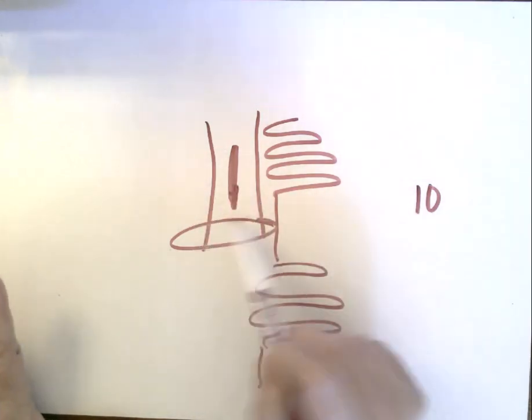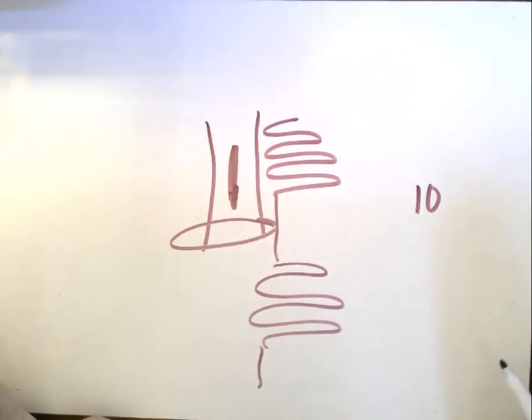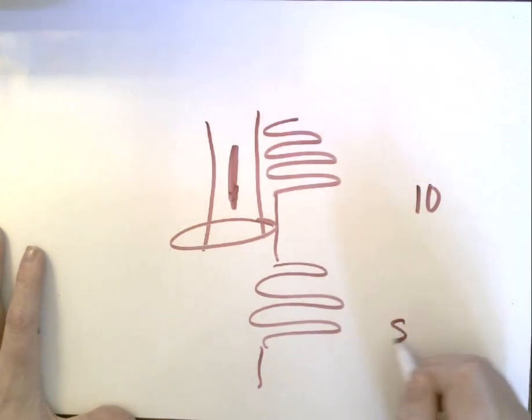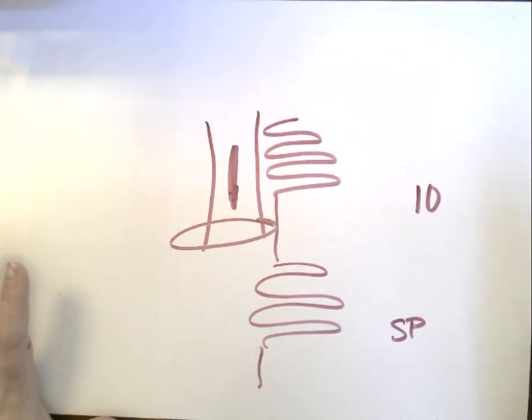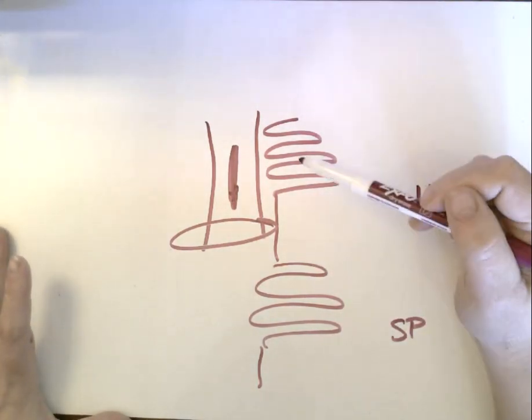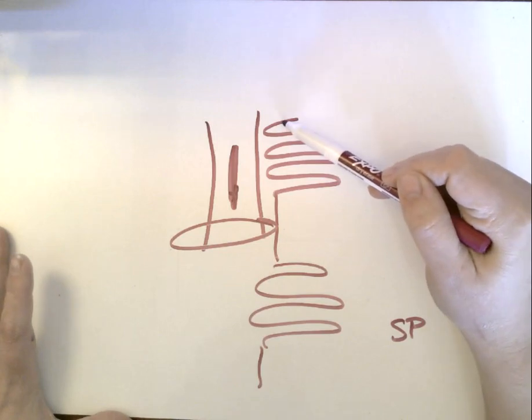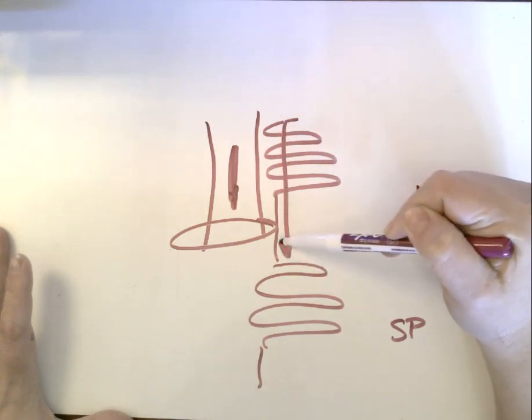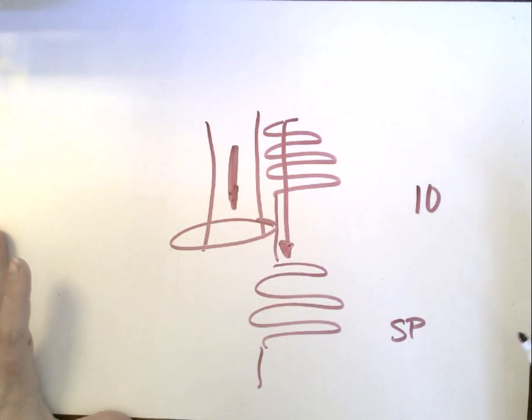With the most intense part of it, the spatial peak. So at no point does the patient not receive all of the beam. That's usually why we are most concerned with spatial peak. And then as far as the pulse goes, the important part is that the patient is getting pulses and some off time too.